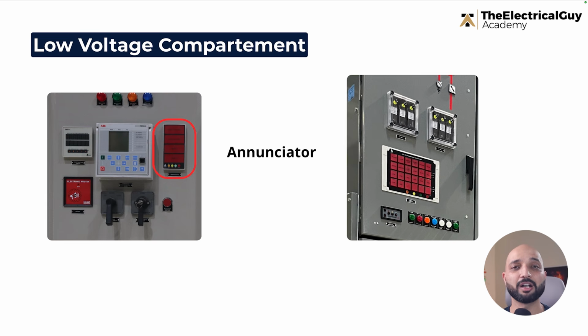Annunciators, on the other hand, are specifically used to indicate abnormal and faulty conditions: earth fault, short circuit, maybe phase to ground fault, the circuit is not healthy, and things like that. Indication lamps indicate the status of things, annunciators indicate abnormal conditions, right? And I'll show you what options they have provided here when we see the actual low voltage compartment.